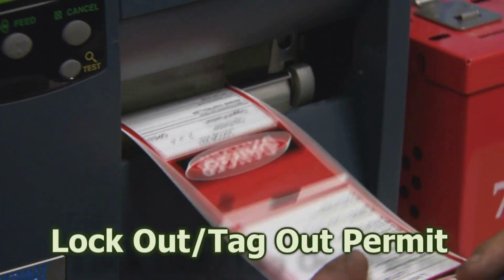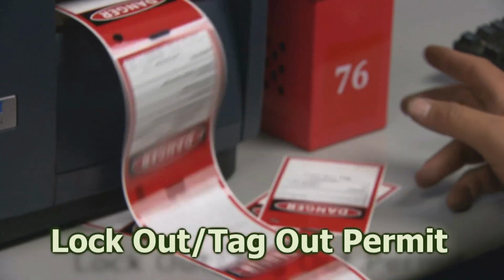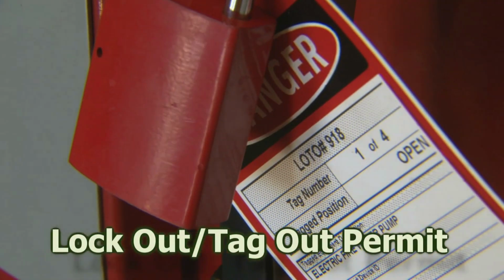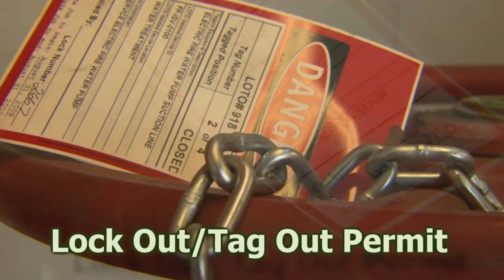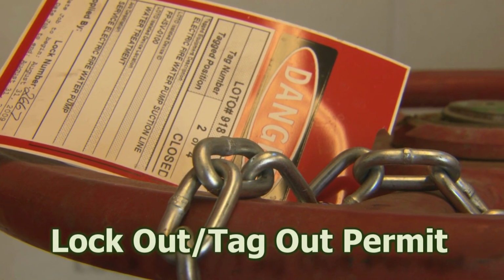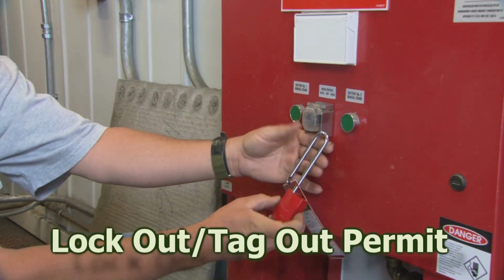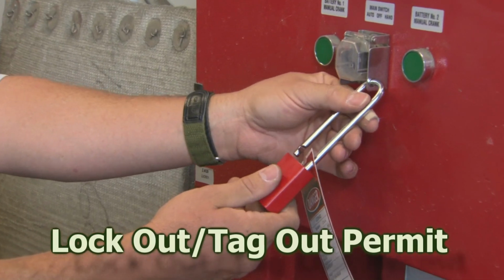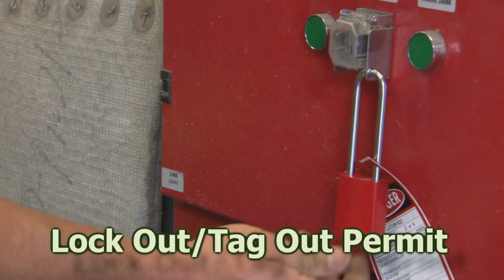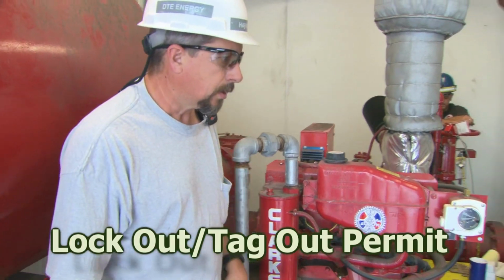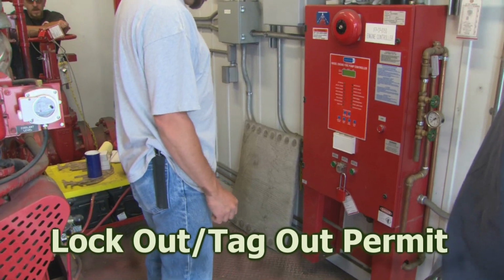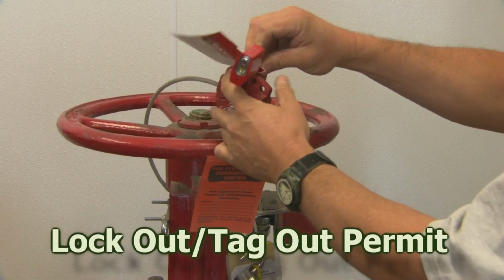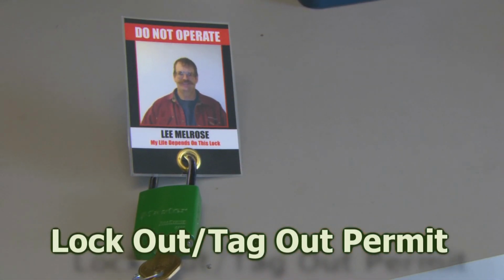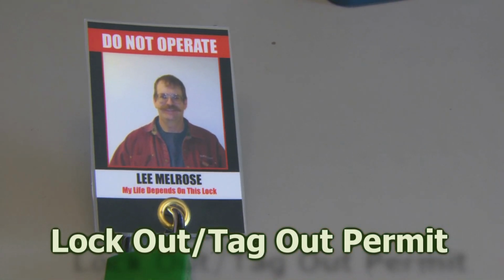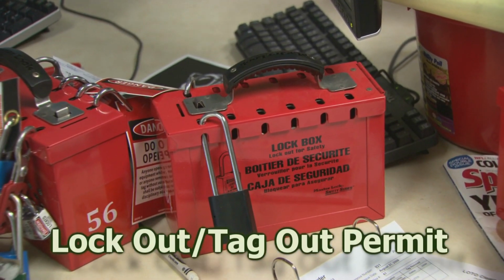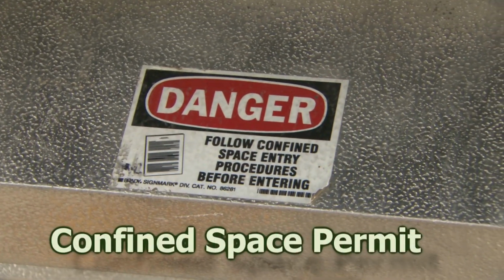completion requirements. A lockout-tagout, or LOTO, is energy isolation, and all energy sources, regardless of magnitude, shall be isolated so that no one is exposed to hazardous energy while working on equipment. Plant Operations manages all LOTO processes and will not authorize work on any equipment until the LOTO clearance is completed. All energy sources are isolated, locks and tags are hung, redundant verification is completed, and affected systems are walked down with affected individuals. Everyone involved in work on equipment under a LOTO clearance shall be signed onto the LOTO clearance with a personal padlock hung on the LOTO lockbox in the TS Power Plant control room.